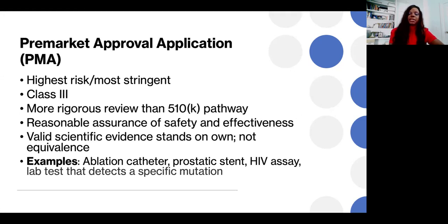So pre-market approval applications, again, these are the highest risk devices, and this is the most stringent review at FDA. It's more rigorous than the 510(k) pathway, and it's applicable to class 3 devices. We have to show that there's reasonable assurance of safety and effectiveness, and we have to provide valid scientific evidence that stands on its own. This is not the same as substantial equivalence, because if you remember, for the 510(k) pathway, we are comparing head to head with a predicate device, a device that's already on the market. But with a PMA, you have to show that this product can stand on its own. So it's not the same comparison.